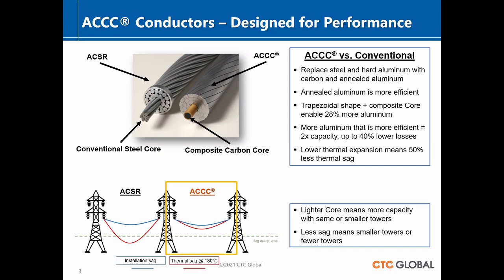For new lines, it also means that you can have shorter towers or towers that are further apart. That becomes part of the equation in the use of advanced conductors if you want to include that in the design. As for efficiency, because you've got more aluminum and it is annealed aluminum, it is more conductive, so the resistance is lower. The efficiency of this is higher than the ACSR. In fact, the reduction is 25 to 40%, depending on the application and how hard that line is being run. You get substantial reductions in resistance, a great increase in efficiency, and that translates directly into energy savings.